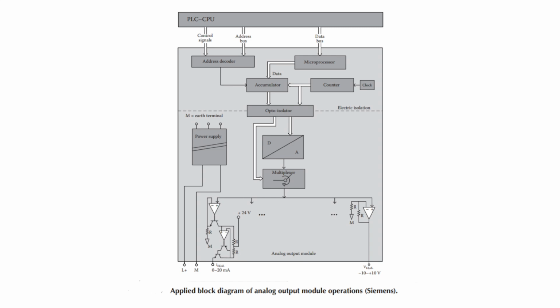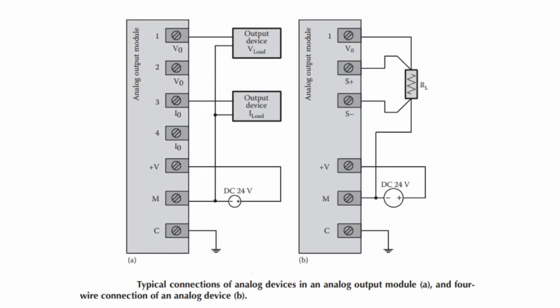The figure clearly shows the typical connection of analog output devices to an output module. Some modules offer a 4-wire connection, as shown in figure B, for higher accuracy in the voltage application. This setup uses two additional wires, seen as S plus and S minus, which are connected directly to the load RL. These wires allow the module to measure the load voltage directly so the necessary corrections can be applied. The most common reason for discrepancies between the desired and the actual output value is the voltage drop in the connecting wires, which occurs mainly due to poor terminal contact.